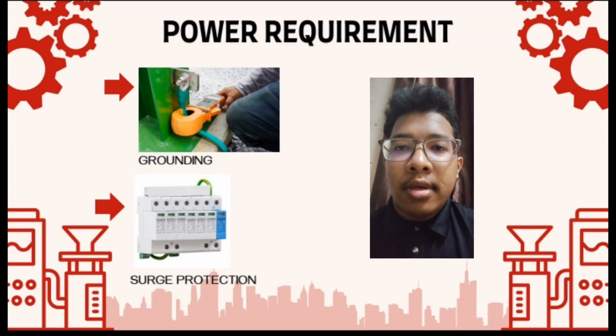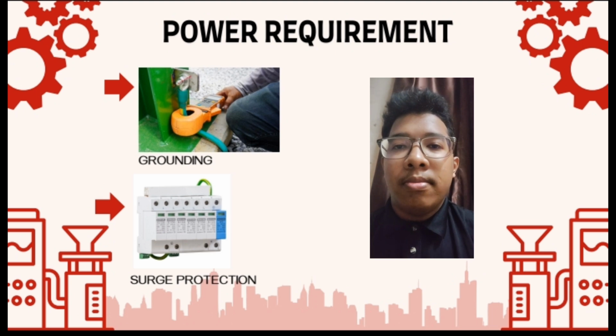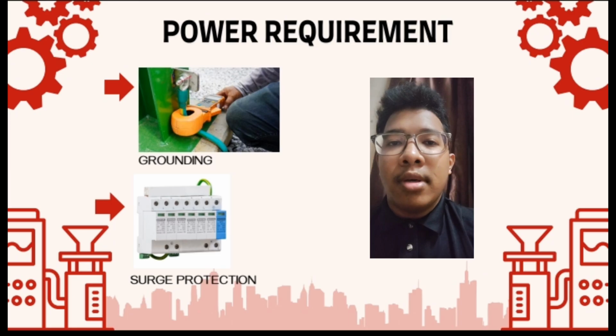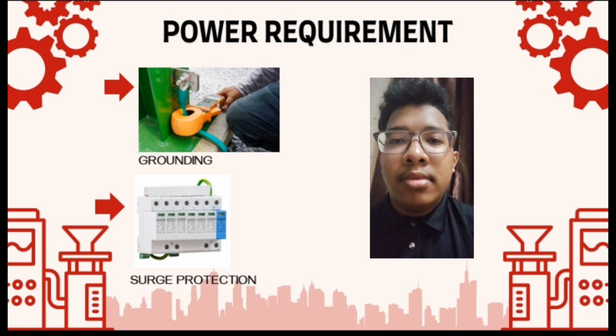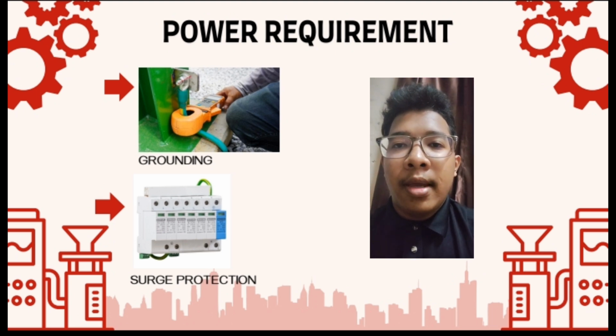Third, power requirements. Confirm the electrical supply type, voltage, number of phases, and expected load. Verify that incoming cabling, breakers, and grounding meet both machine requirements and local code. Plan the routing from main distribution to the machine, and ensure disconnects and protective devices are accessible. If the machine requires a dedicated transformer, soft starter, or surge protection, specify it during planning. Also confirm any temporary power needs for testing. In summary, a careful site inspection, a properly designed foundation, and verified power arrangement are essential. Doing this now will prevent costly rework and safety issues later.